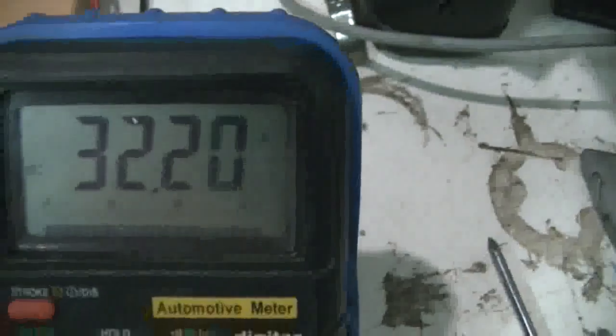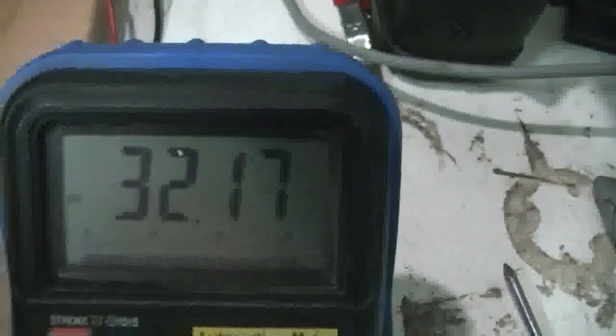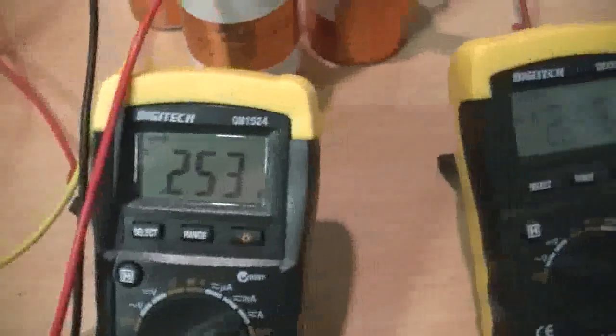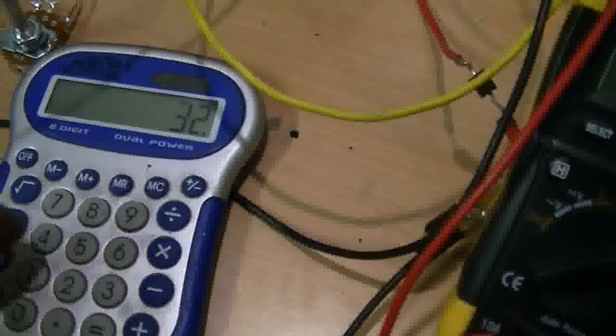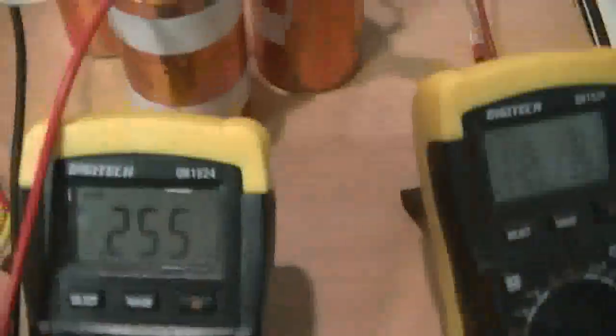So we're down to 2.8. The voltage is 32 point... we're going to go 32.1. 253 milliamps. Oops, 32.1 times 0.255. 8.1 watts now coming from those caps. 2.8 watts including the transformer losses being fed into those caps.